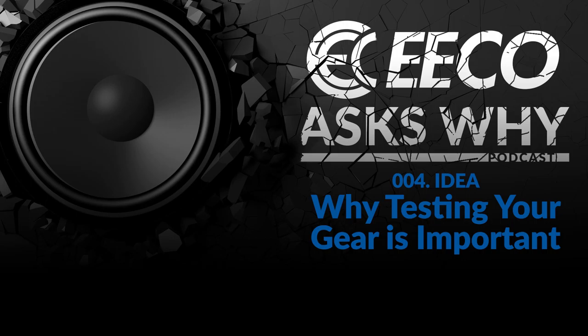Sure. You can walk into an electrical room or take a look at any sort of electrical facility, and you can kind of gauge whether the equipment is in good working order or whether it's in need of some TLC. A lot of our testing, although we're calling it electrical testing, is testing the mechanical integrity of our system. It's testing the mechanical integrity of our bolted joints through copper bus. It's testing our electrical integrity of our cables and the cable runs. It's testing the mechanical integrity of our breaker mechanisms and making sure that they're operating properly. So it's important to understand that although we're performing electrical tests, we're actually testing the mechanics of this system.